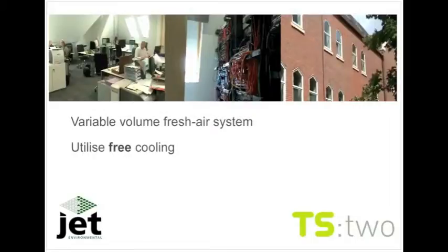From historic temperature records, even in peak years, the average daily external temperature is below the internal design requirement. For large parts of the day, free cooling is available from the external conditions. This is particularly true during the night. This nighttime purge has the effect of pre-cooling the structure to offset or delay heat gains during the following day's occupancy. The system also utilises a proportion of recirculation air when full fresh air is not appropriate and redistribution of energy may be of benefit.